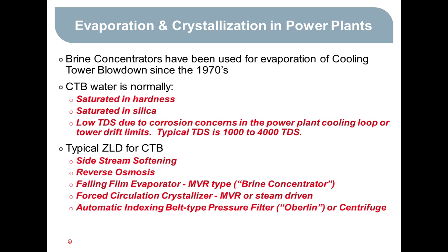It's generally not too high in TDS because the cooling tower has limits on how high you can concentrate without getting into problems with drift and also with scaling in the cooling loop in the power plant. The typical zero liquid discharge system that's evolved over the years for cooling tower blowdown usually involves almost all of the steps shown here. Side stream softening to get rid of some of that hardness, some of the calcium and magnesium that causes scaling. Then a reverse osmosis step, because the TDS isn't too high, so we can get some concentration in an RO system, followed by an evaporator, which is typically an MVR.